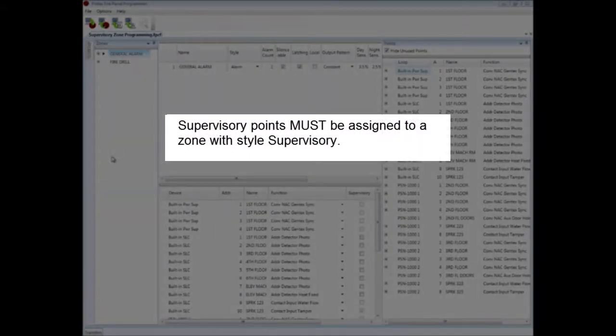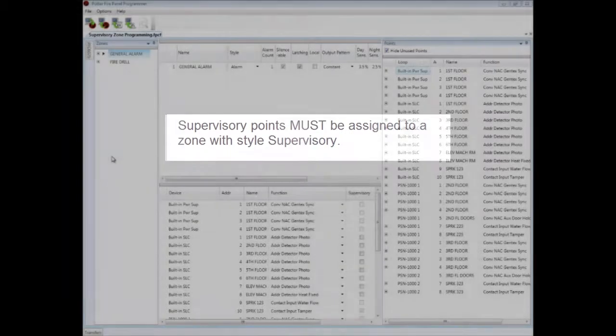In the PFC 6000 series fire alarm control panels, if you have a point that is a supervisory condition, that point needs to go in a supervisory zone.